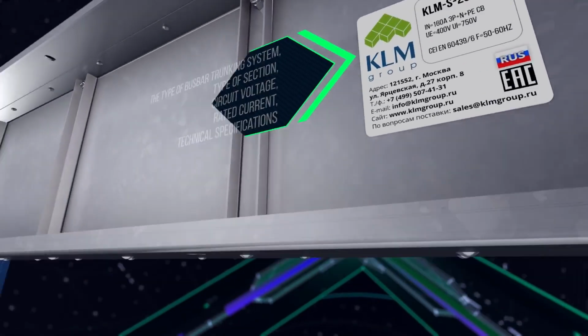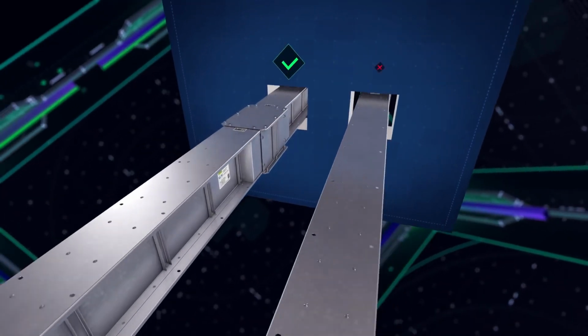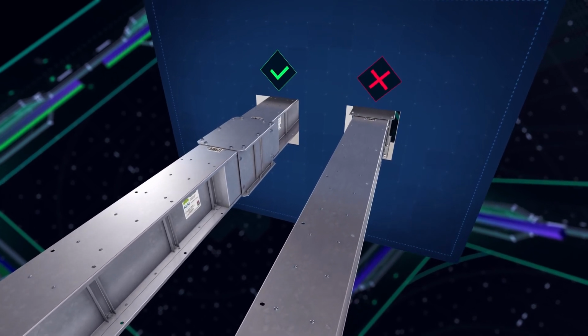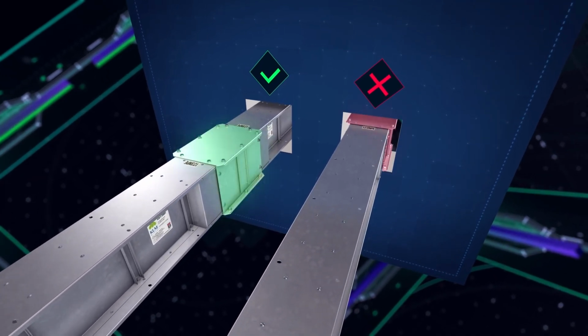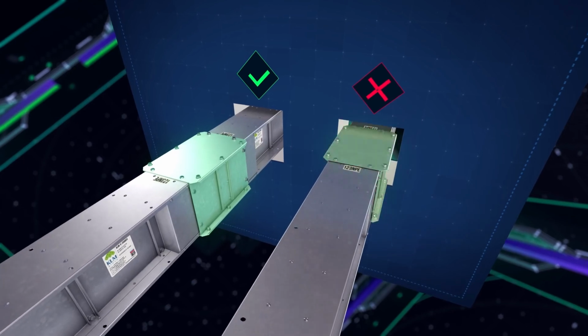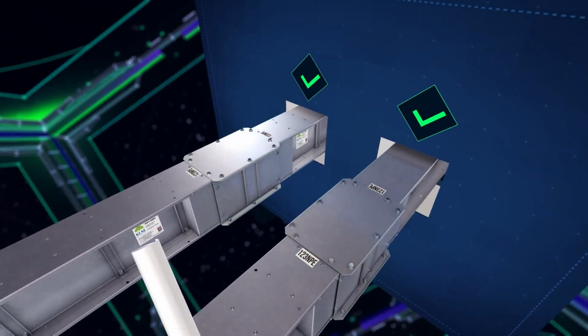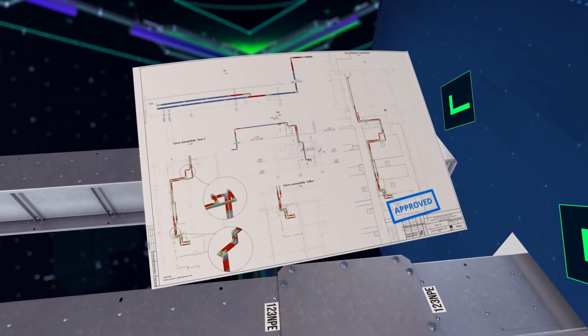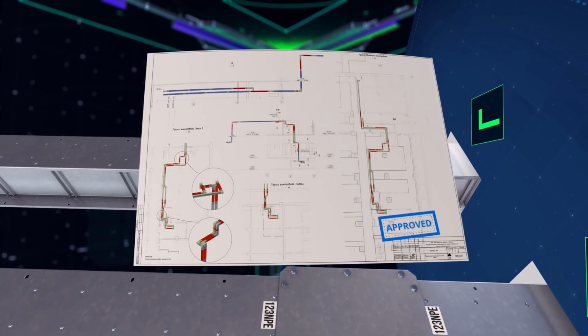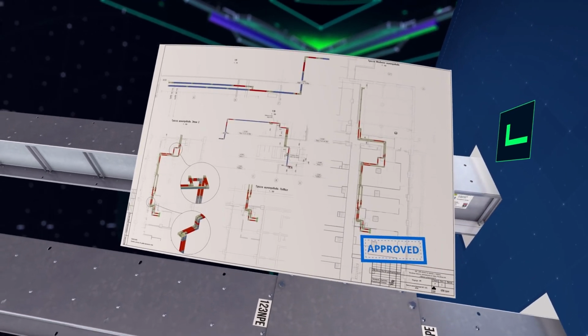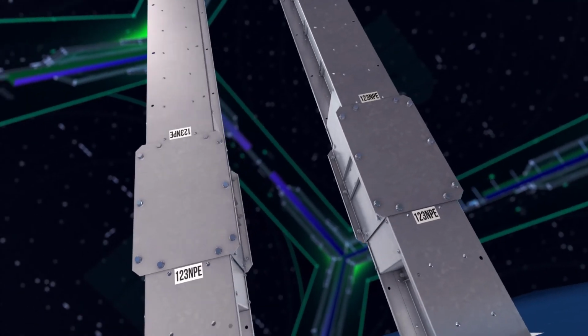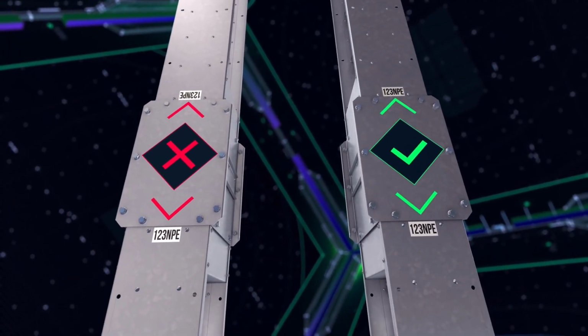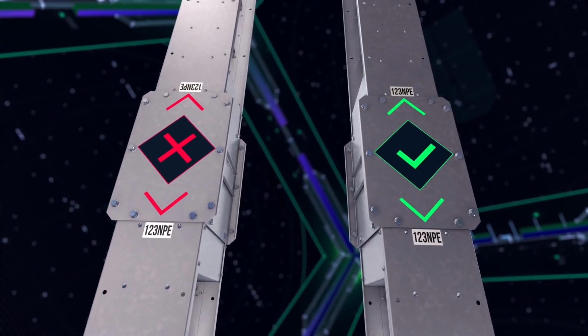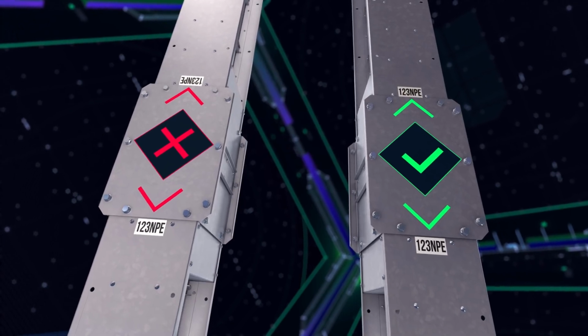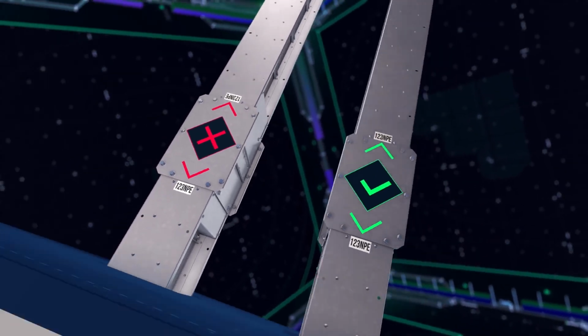The drawing of the busbar trunking system route and the design of the facility must be studied carefully. Junction units must not be placed in floor, ceiling assemblies or in interior partitions of a building. Care must be taken to ensure that the busbar trunking system is assembled according to the approved drawing, unless the contract supervisor indicates otherwise. Special attention must be paid to proper location of the conductors in all sections of the route, including where sections of the busbar enter electrical panels.